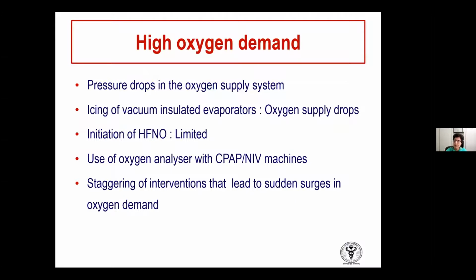Or the patient is on CPAP or NIV and wants to eat, and because they're not able to maintain saturation, you shift them to HFNO - there is a sudden surge and increase in oxygen requirement. So these interventions should be staggered, and not all patients should be given these at the same time. If really required, these should be done so that there are no sudden pressure drops in the oxygen supply system.